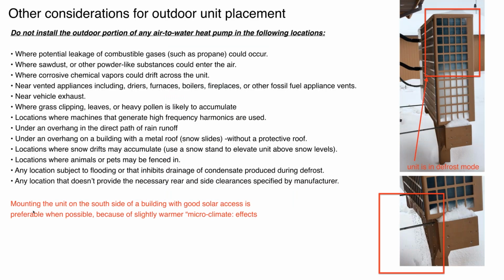Okay. Now, what are other factors? Well, basically, we don't want sources of moisture around the outdoor unit. And the reason for that is if we have, for example, a dryer vent, or if we had a vent from perhaps a gas-fired boiler in the house, that produces a lot of water vapor coming out the vent. That coil is cold. It's definitely colder than the outside air temperature. So imagine it's 10 degrees out. That coil is going to be at a sub-zero temperature, and any source of vapor around it is going to freeze against that coil and just force the unit into more defrost. We want to keep it away from exhausts in general, any kind of an exhaust.